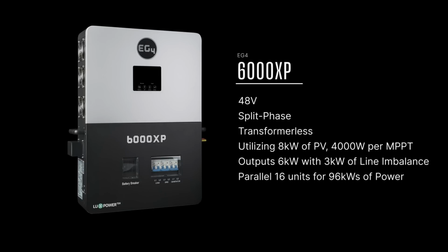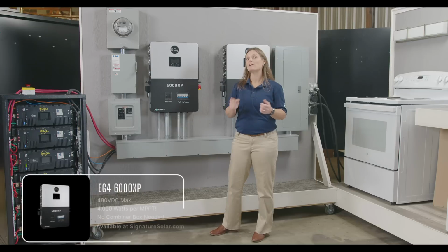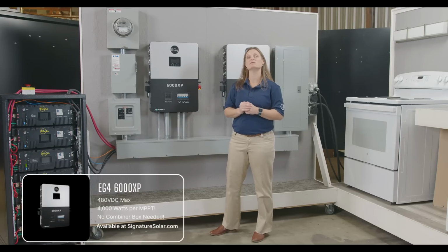It's a 48-volt split-phase transformerless inverter that can utilize up to 8 kilowatts of PV. That's 4,000 watts per MPPT, while efficiently outputting 6 kilowatts of power. That's 3 kilowatt line imbalance. And get this, you can parallel up to 16 units for a whopping 96 kilowatts of output power. How about its peak voltage at 480 volt DC?